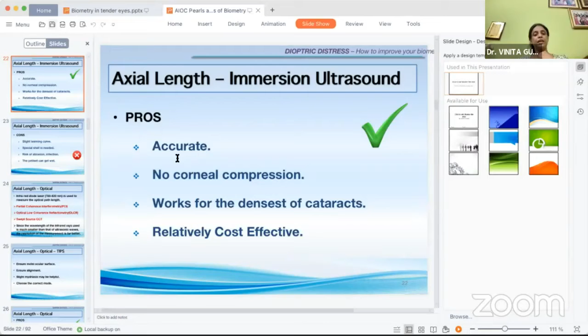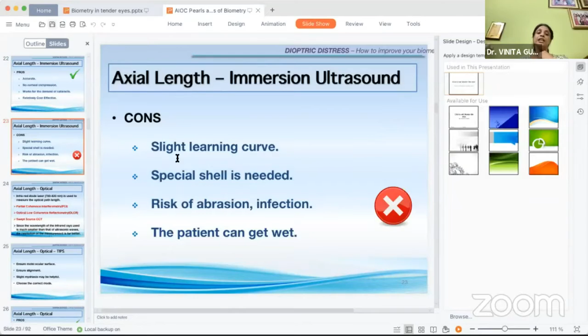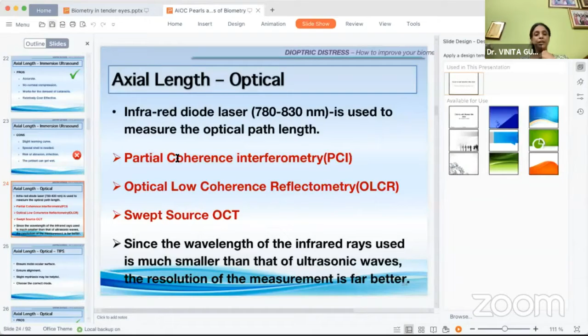So for the optical biometry, as we have already mentioned about the immersion ultrasound using a Prager's shell, obviously the advantage of immersion ultrasound is accuracy increases. Other advantages of ultrasonic mode are there, but the disadvantages are similar, and the added disadvantage is the patient can get wet. So the better option is obviously to use an optical biometer, where we are using infrared diode lasers, and we have different machines based on different types of technology. We have the partial coherence based interferometers, we have OLCR based biometers, and we have swept source based biometers.